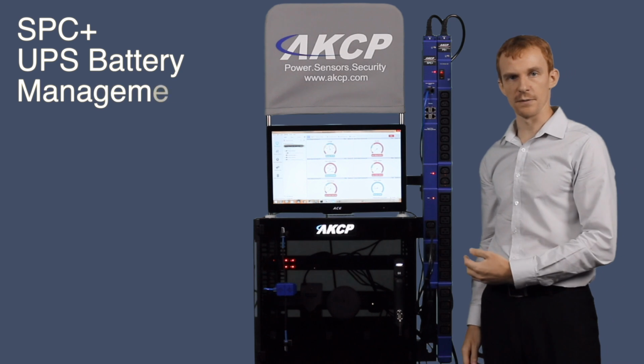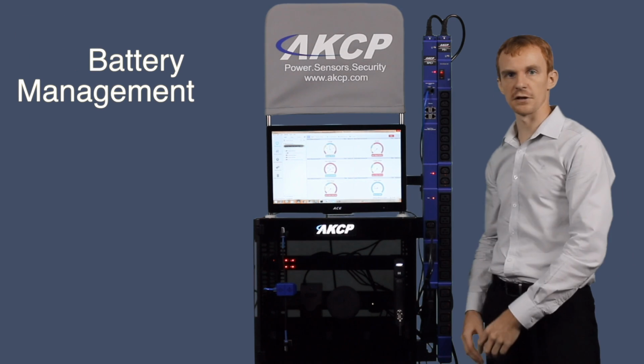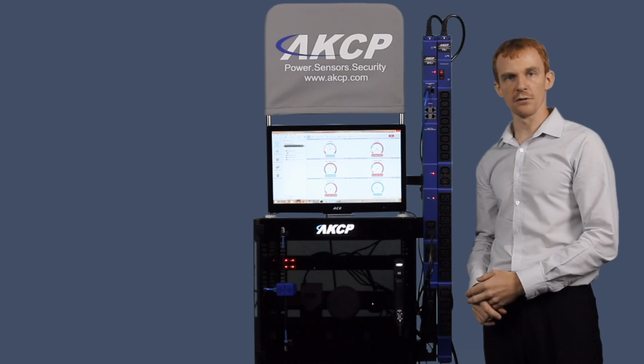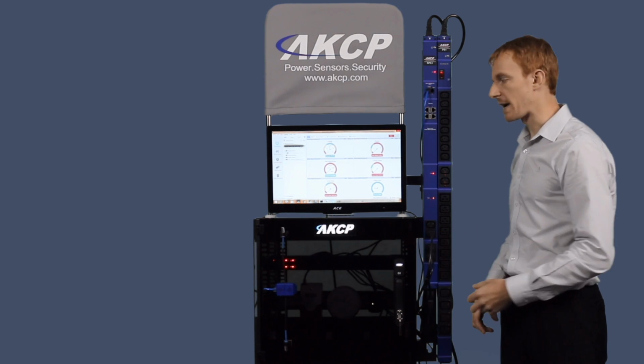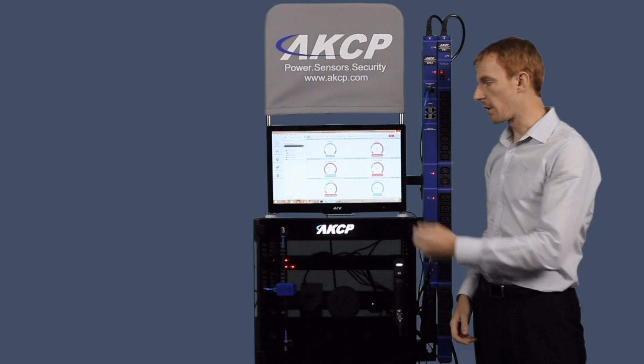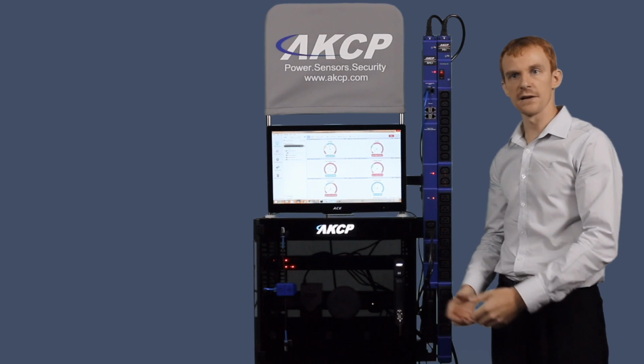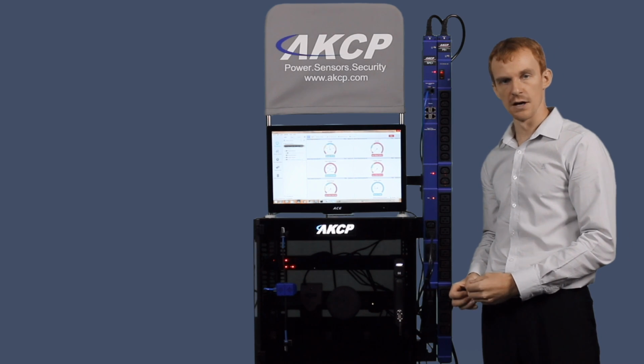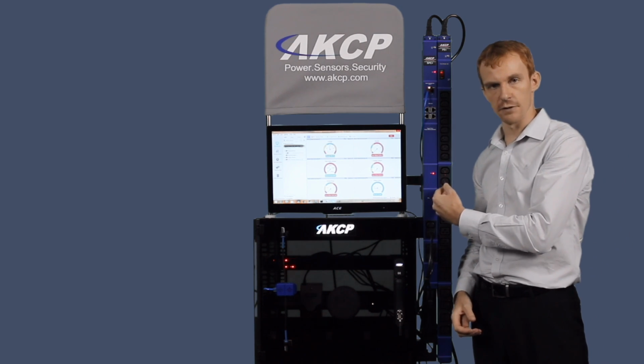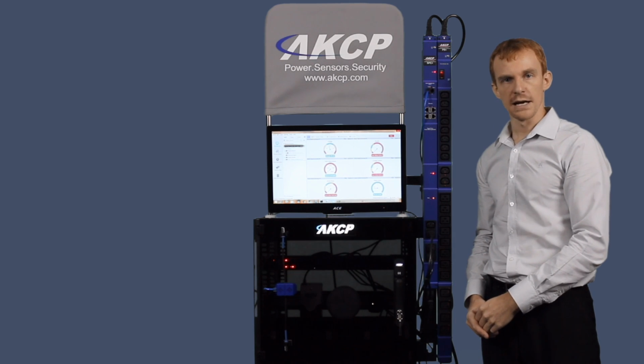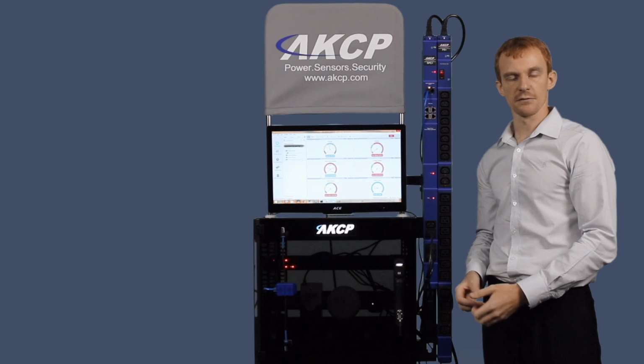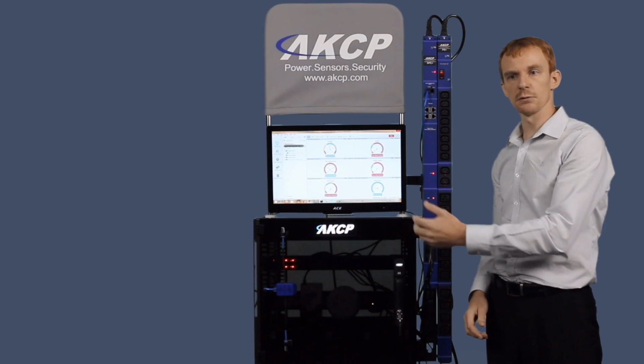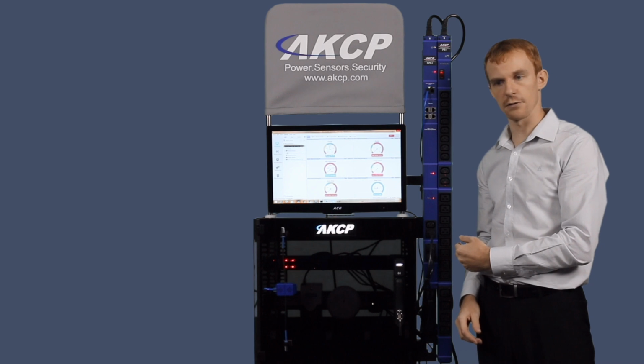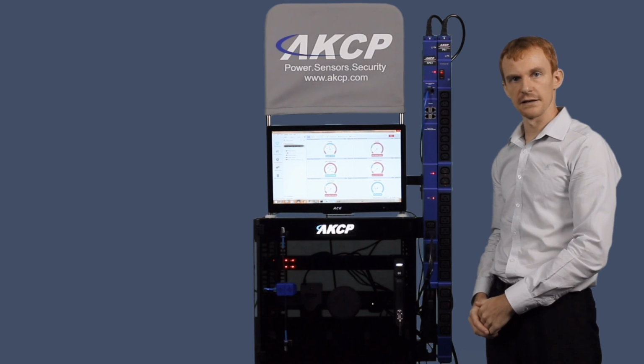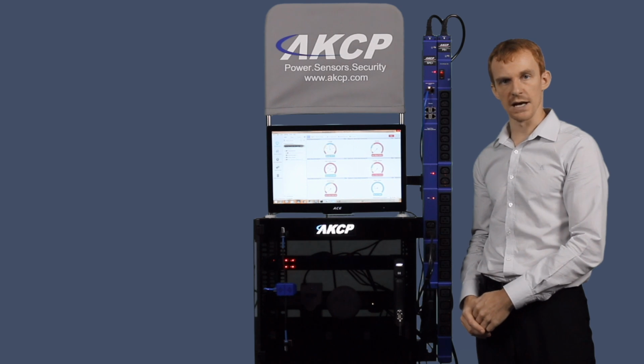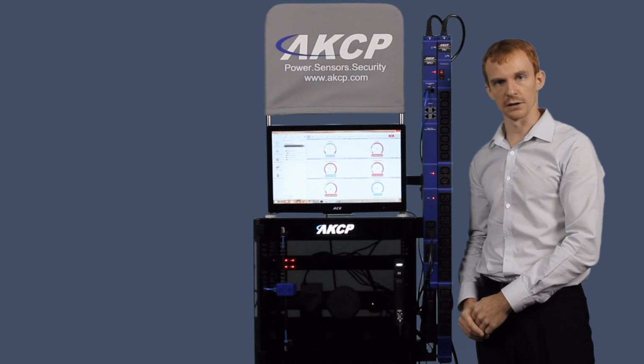Another important feature of the power meter is our ability to monitor through AKCPro Server not only the power being consumed but also any attached UPSs. Your UPS battery backup, if it is SNMP enabled, can be monitored via virtual sensors in AKCPro Server. In the event of your AC main line power going down, we can monitor the power being consumed by your IT equipment versus the power available in your UPS. We can then send alerts when your UPS battery level gets critical, and this will allow you to respond by shutting down non-essential IT equipment by using our built-in relays, and this will preserve the battery life of your UPS, ensuring that your critical IT equipment will remain online.